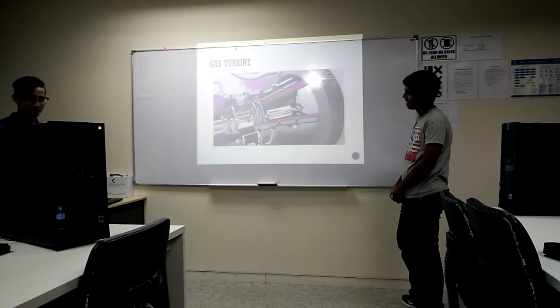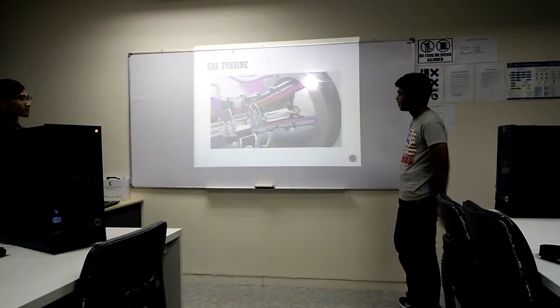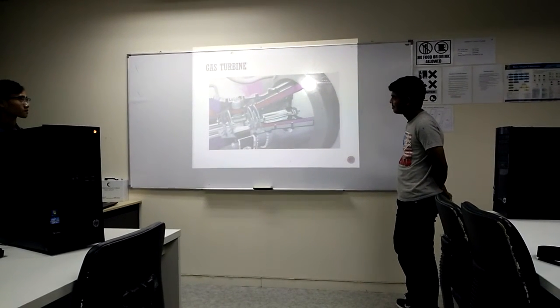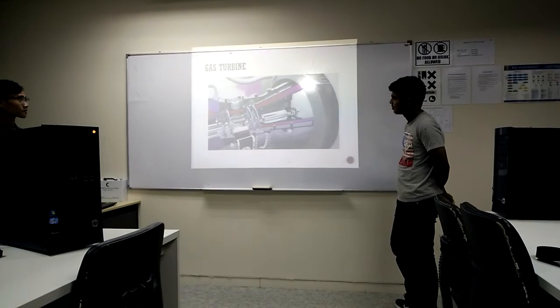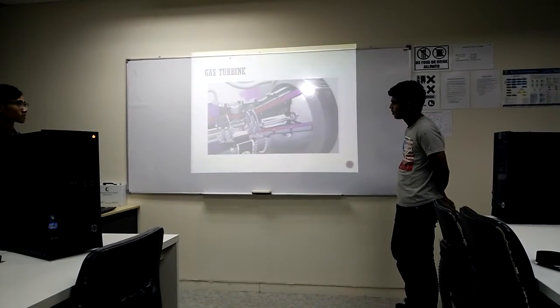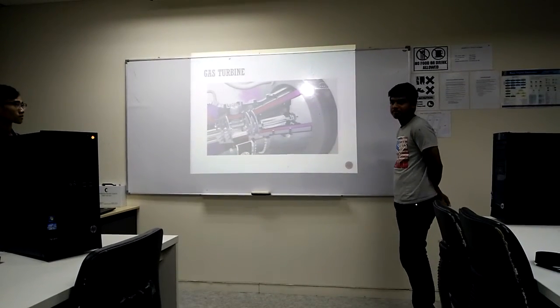The shaft of the power turbine can be operated independently of that of the gas generator at a speed range of 45 to 105% of the nominal speed of 12,600 RPM, and thus adapt optimally to the requirements of the machine to be driven. However, such a flexible speed range is not necessary to generate power.